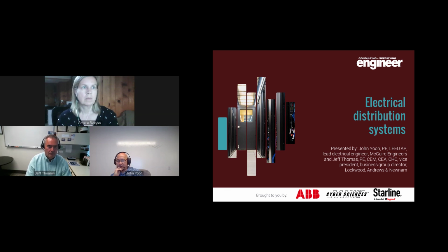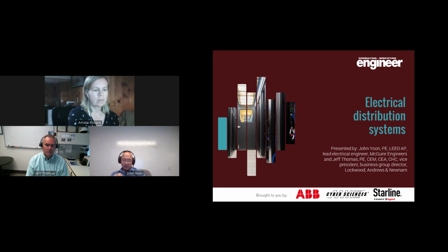Sure. So with zone selective interlocking, you have multiple breakers in series, each with an electronic trip unit and all interconnected through a communication bus. So these breakers can communicate with each other, and you can basically communicate where a fault is happening with respect to any of those individual breakers.